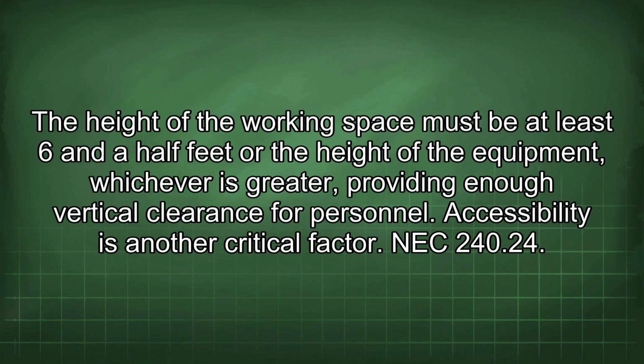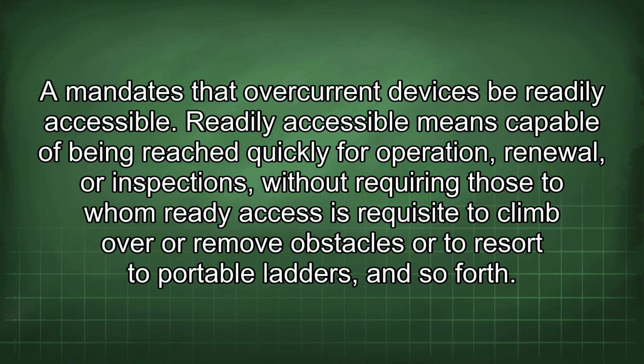NEC 240.24 mandates that overcurrent devices be readily accessible. Readily accessible means capable of being reached quickly for operation, renewal, or inspections, without requiring those to whom ready access is requisite to climb over or remove obstacles or to resort to portable ladders, and so forth.